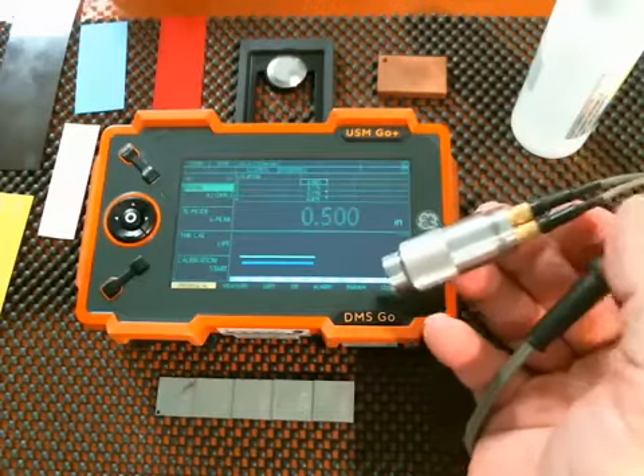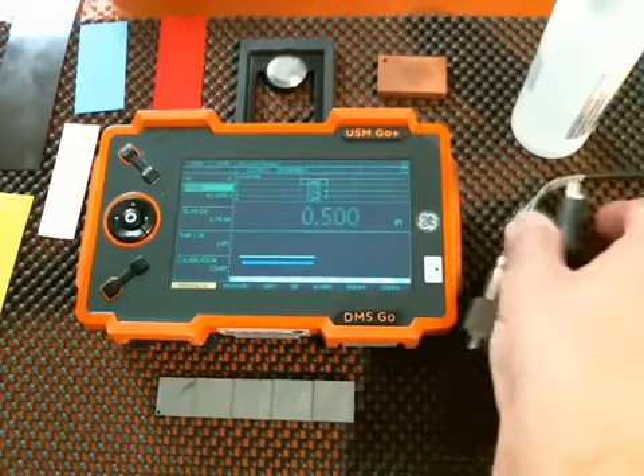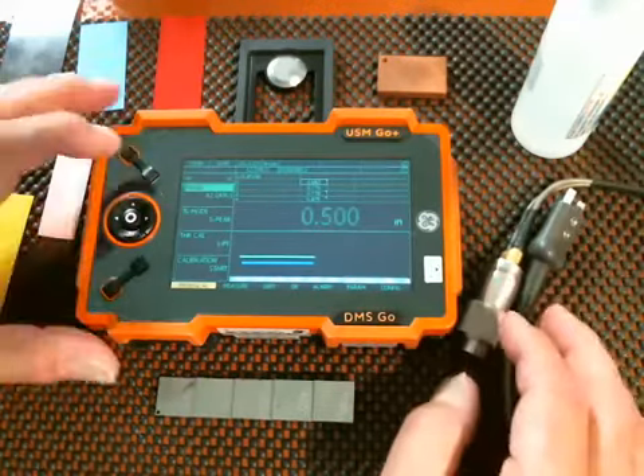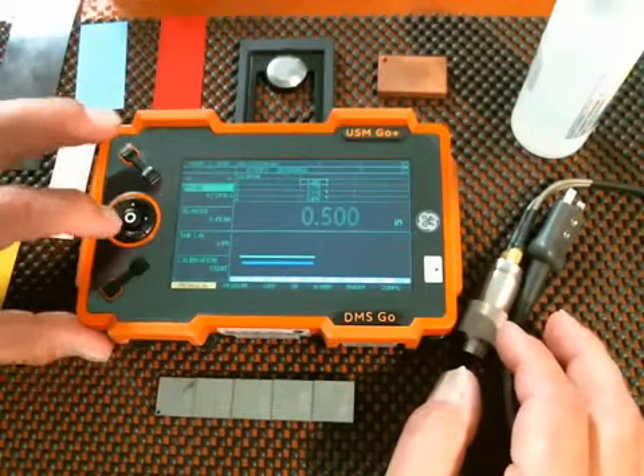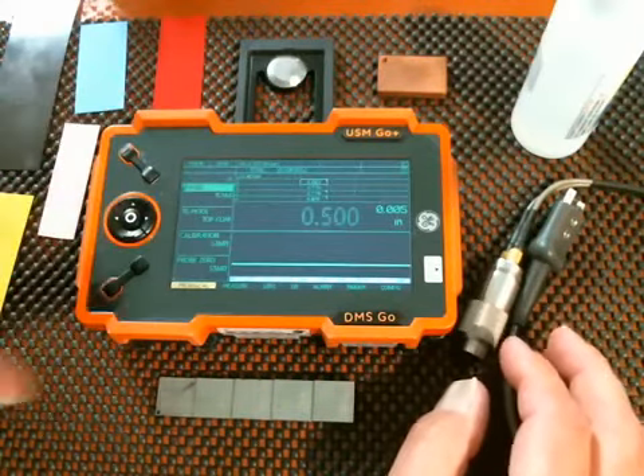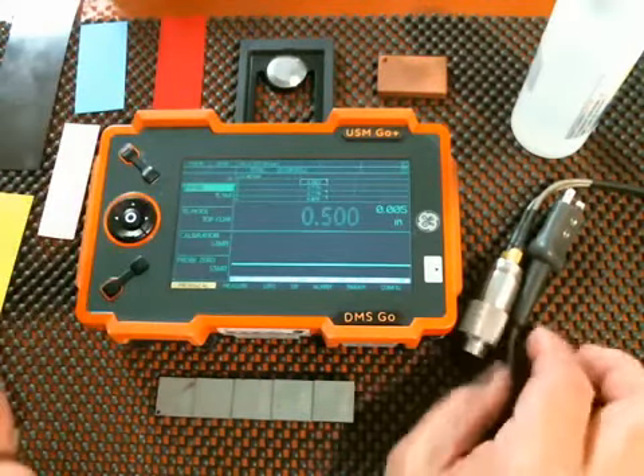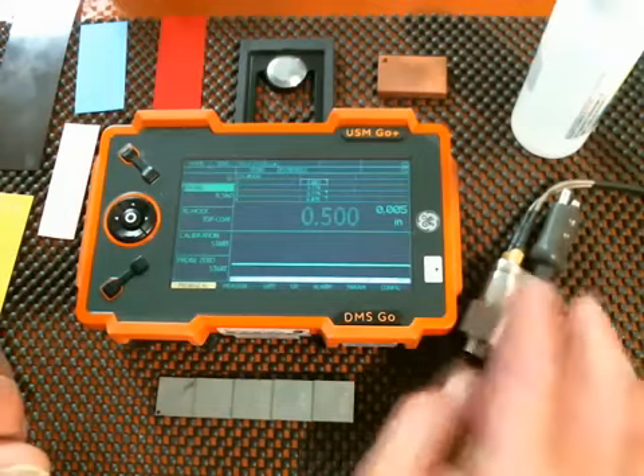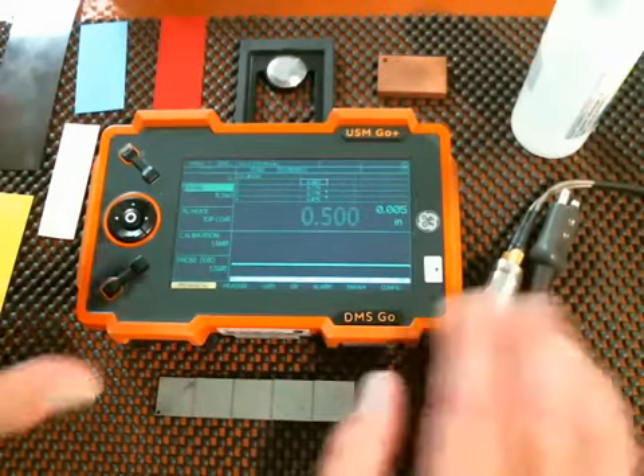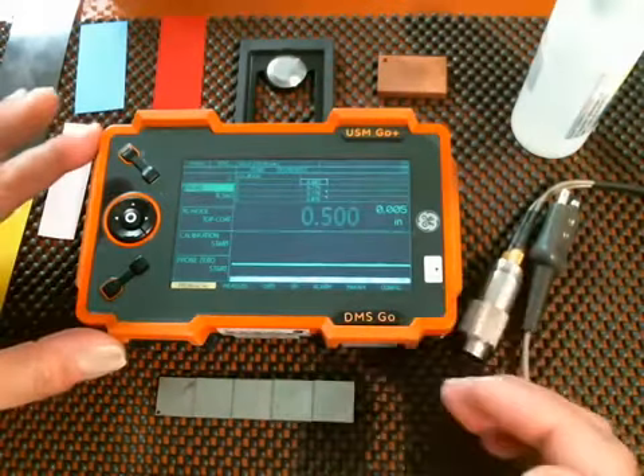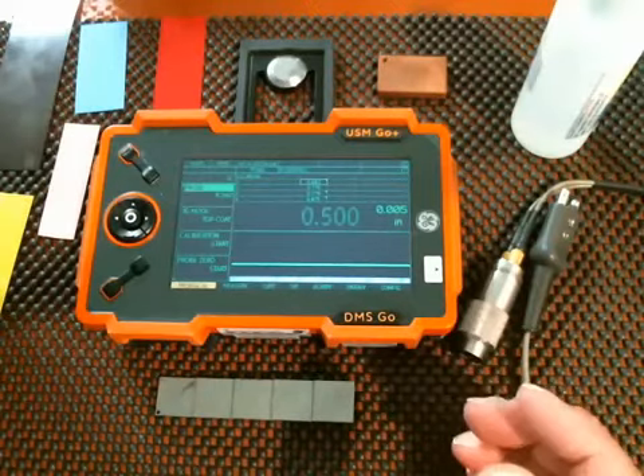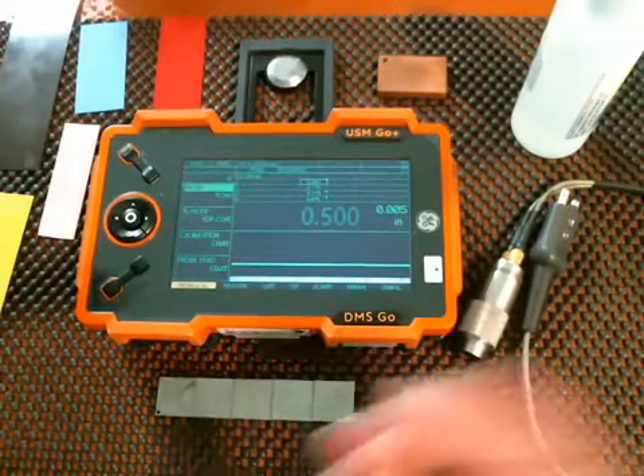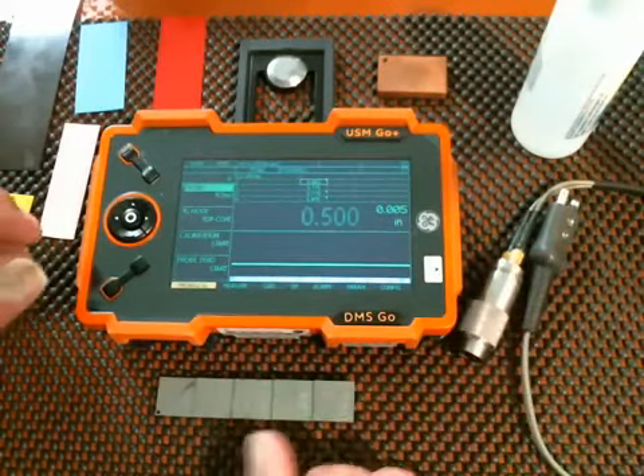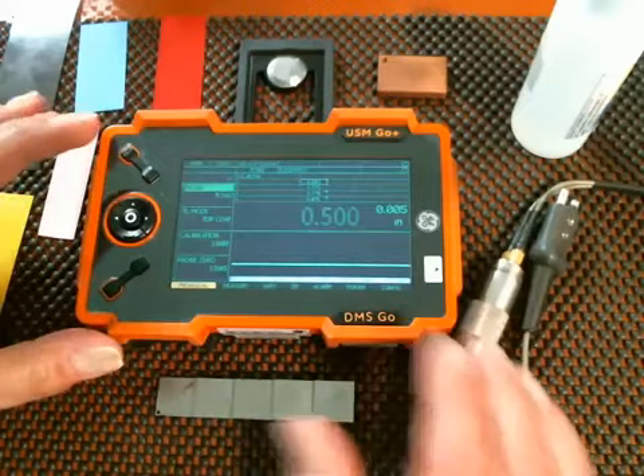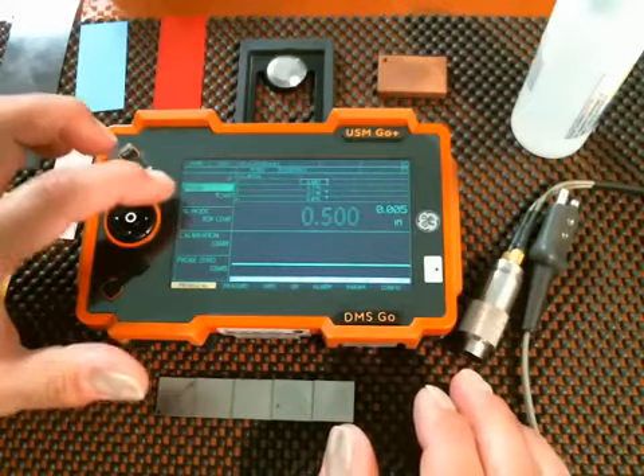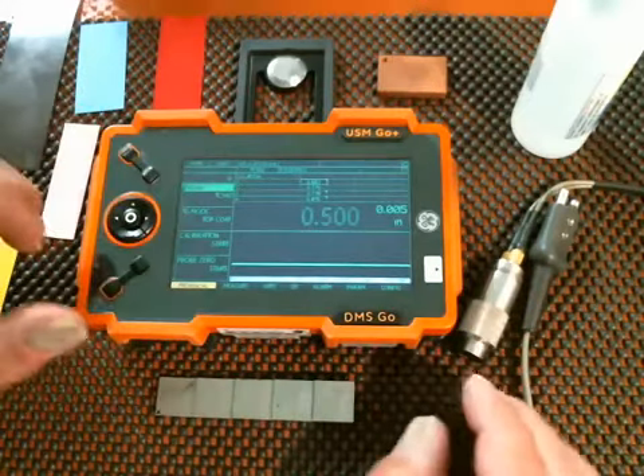First of all is the top coat probe itself. You want to use caution when connecting this to the instrument. You want to make sure you come to probe and select the TC560 probe before you make the connection. The probe uses a multiplexer internally, so connecting it, especially if you happen to have a combined USM Go and DMS Go, if you would happen to connect it in the flaw detector mode with a high energy pulser, you could do some damage to the probe.